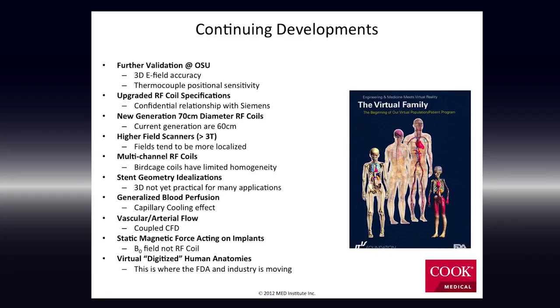Multi-channel RF coils instead of a quadrature-fed birdcage coil. We're going to individually control each of these loops. A multi-channel coil is a way of tweaking these higher field coils to give a more uniform B1 magnetic field at the isocenter. There are no commercially manufactured MRIs that have that kind of coil yet, but you have to be prepared. You can't wait for it to show up and then say, hey, we have to figure out how to do it.